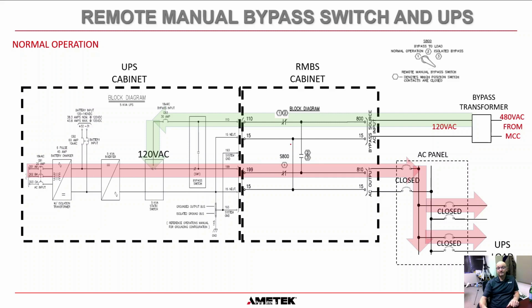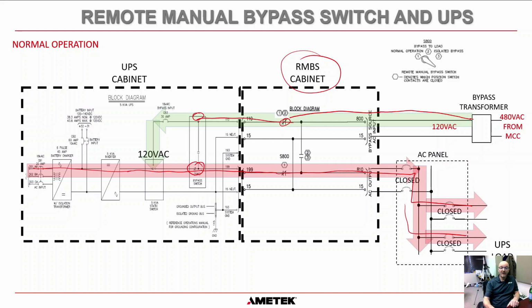So in normal operation, you can see here the power flow is as normal, through the rectifier, through the inverter, through the static switch, through the internal bypass switch contact, out into the RMBS cabinet, through this contact here, and out to the load circuits. That is where the power flows. And we still have our 120 volts bypass coming into the RMBS cabinet, through this closed contact here, through the bypass switch internal to the UPS, and it's ready to go at the static switch here if necessary. Okay, that is when we have the RMBS in position 1 and everything is in normal operation.